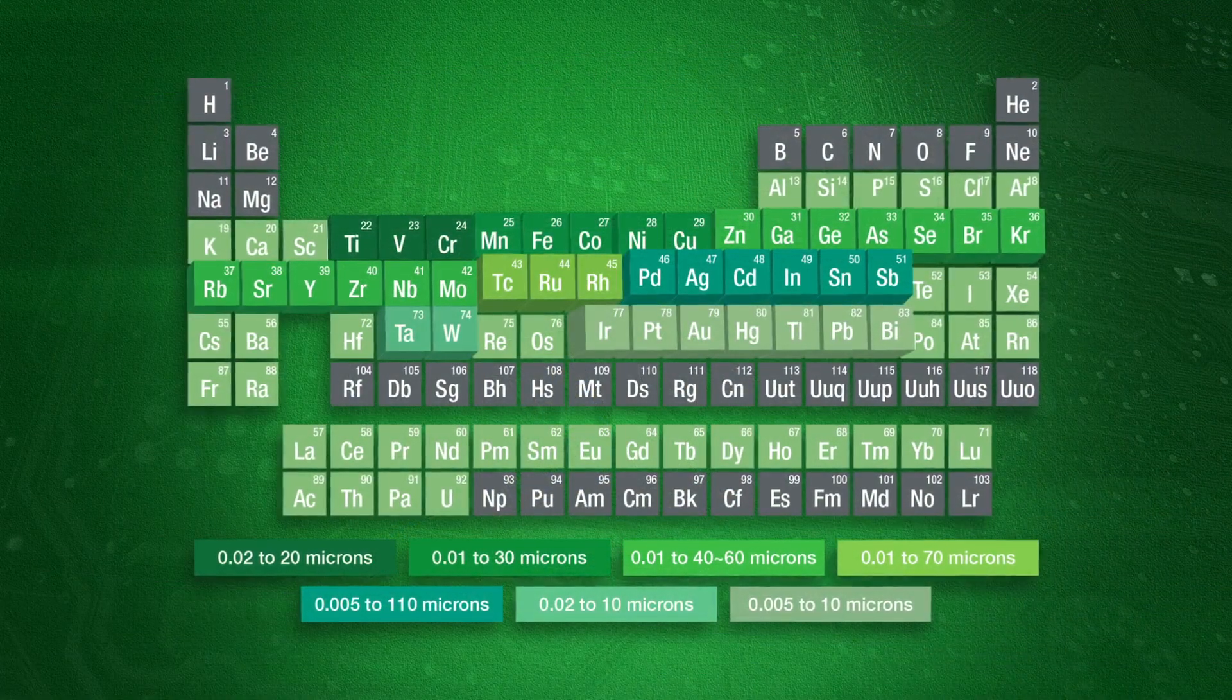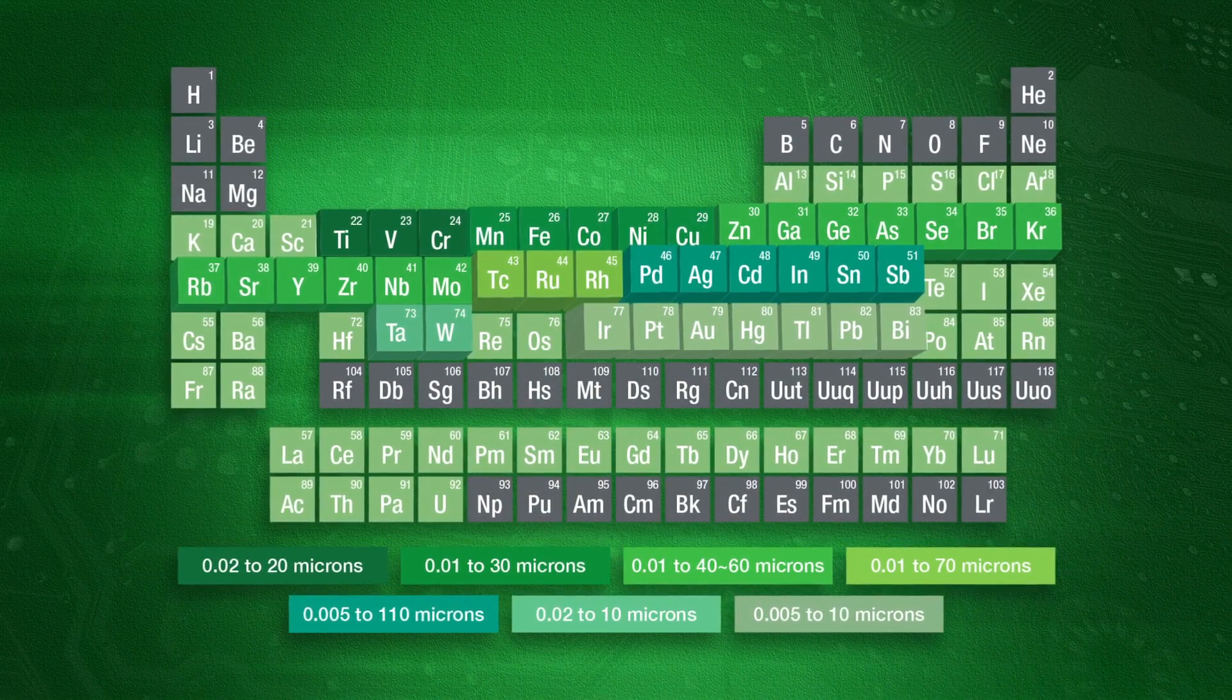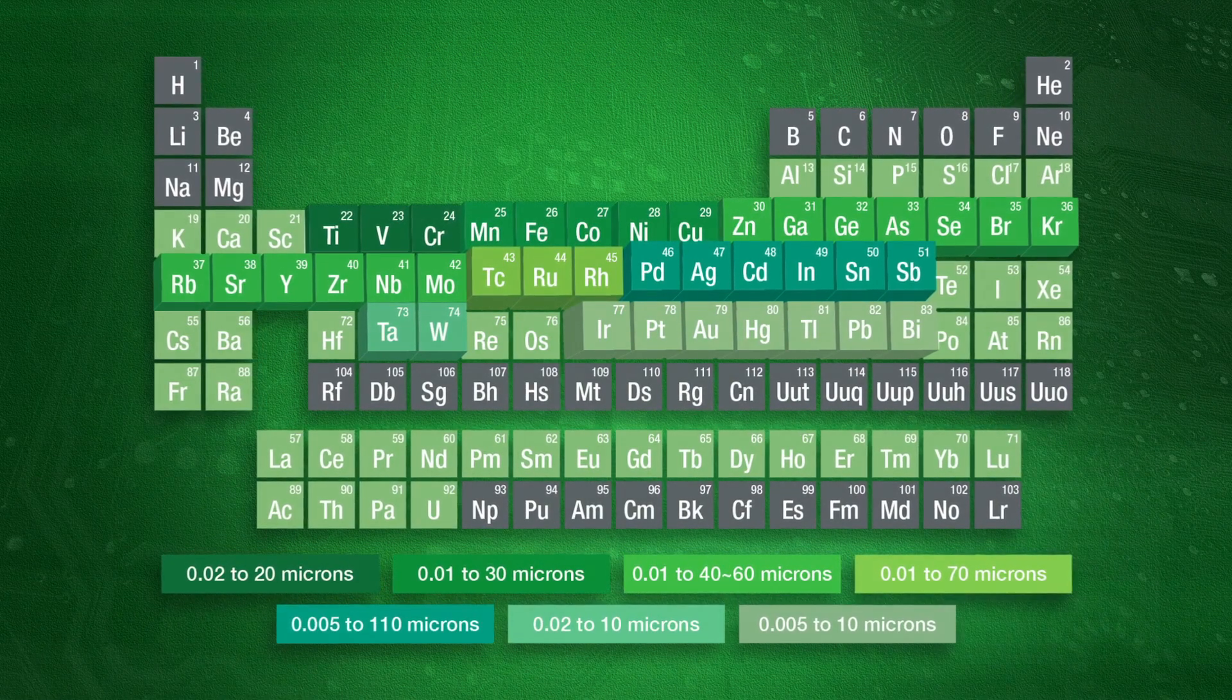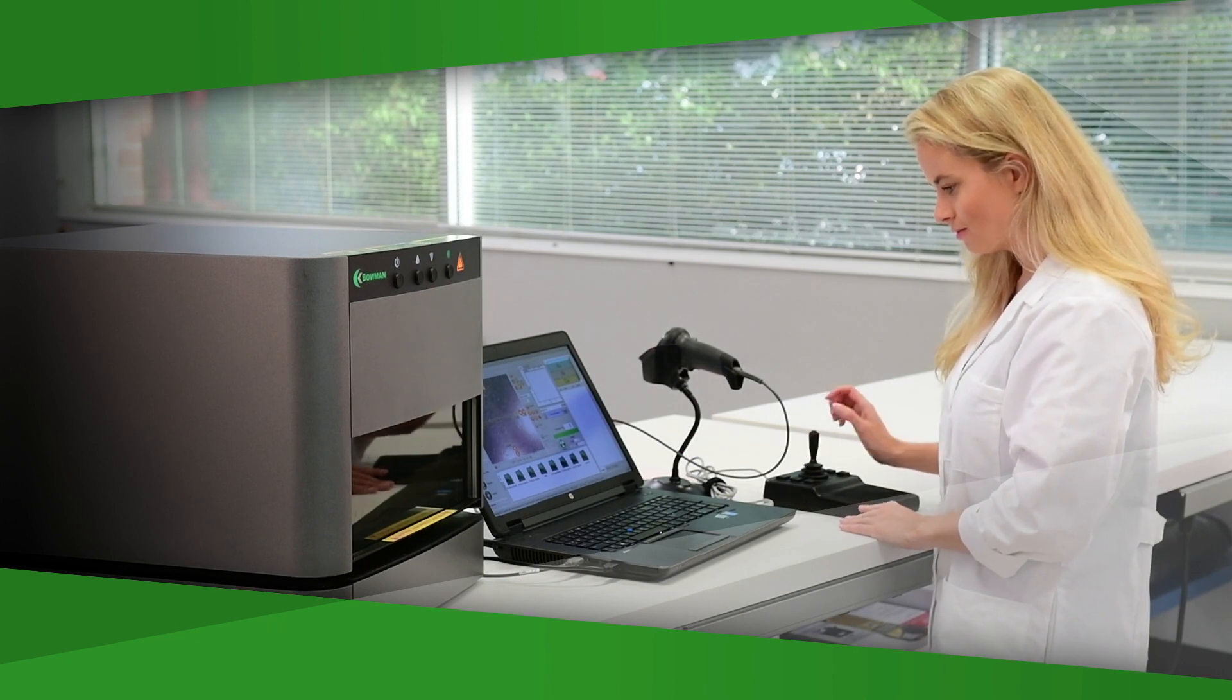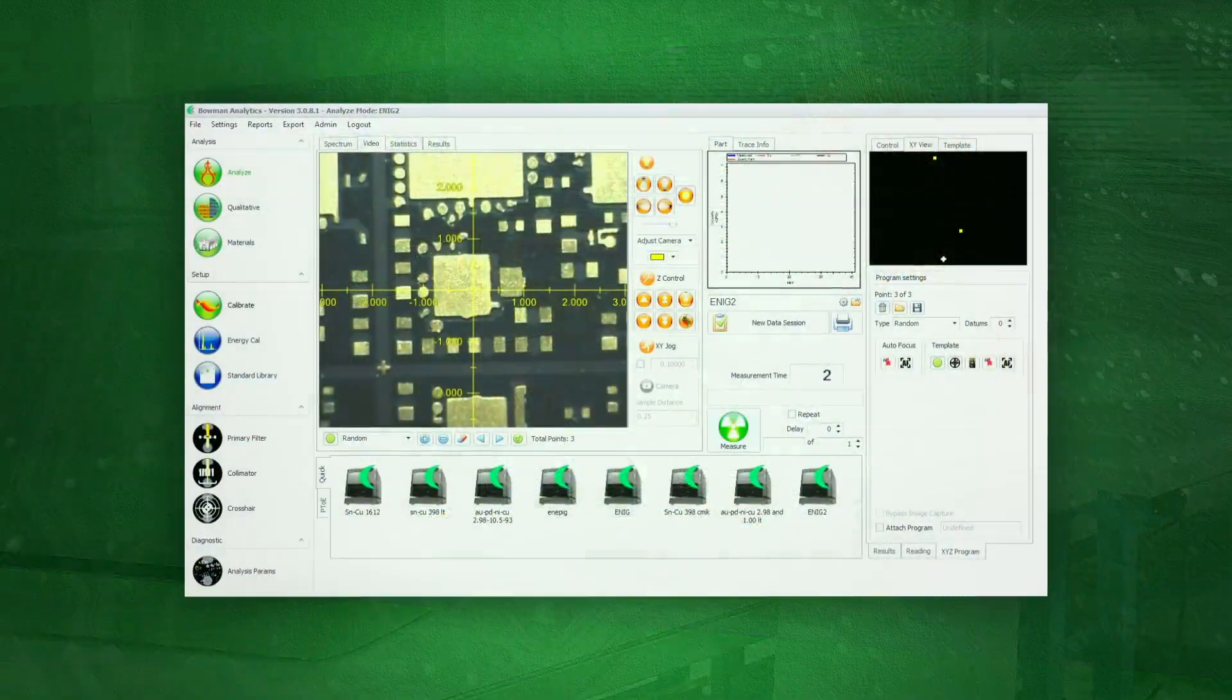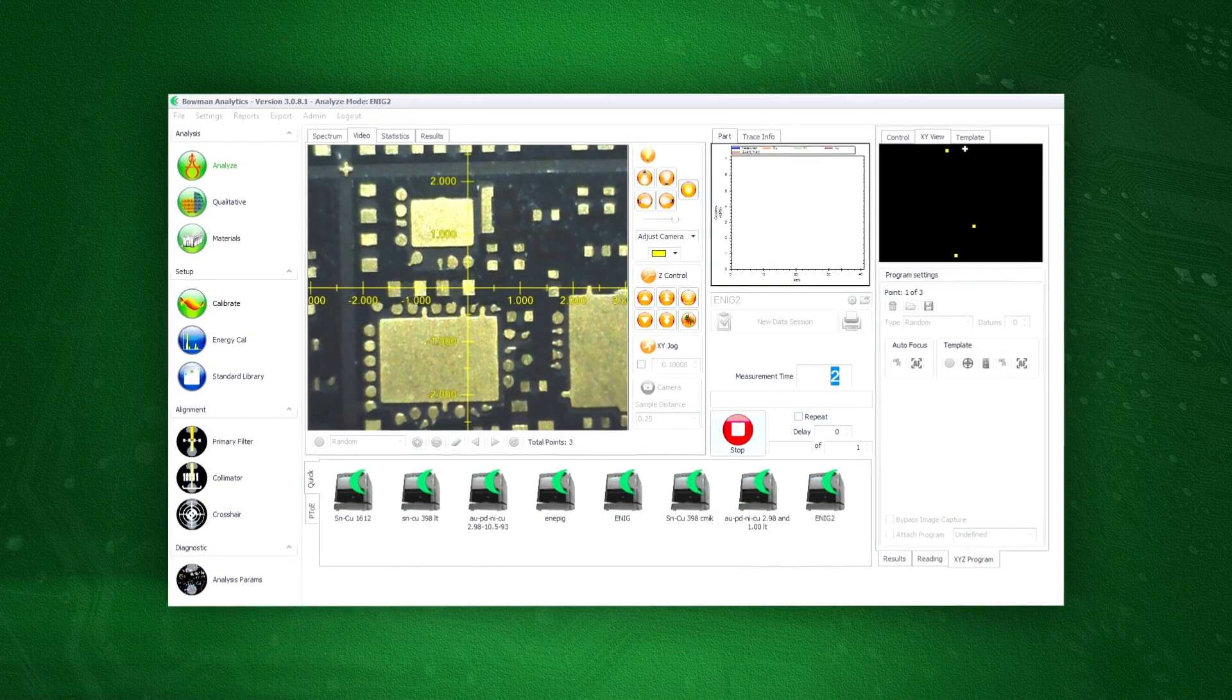Like all Bowman instruments, the P-Series performs composition analysis on up to 25 elements and five plated layers. Advanced pattern recognition enables fast, precise identification of measurement locations for even the smallest structures. Image details or patterns are set using a recognition menu.